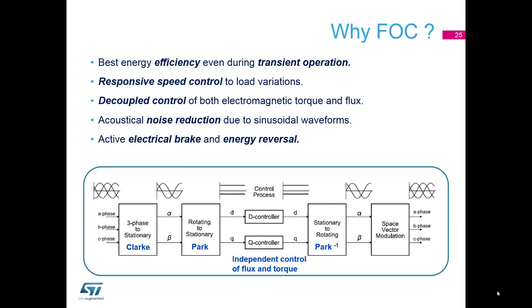The field-oriented control has many benefits over other control strategies, like best energy efficiency. It is as well very fast in the speed control when there are load variations or bus voltage variations. They allow decoupled control of both fields related to the position of the rotor, the torque part, and the magnetization part. And because we drive the motor in the perfect angle orientation with a sinusoidal output, we are able to reduce the acoustical noise. Because the field-oriented control works in four-quadrant operation, it allows to actively brake and get back the energy stored in the system to our power stage and further to the battery or our power distribution system if the construction allows that.